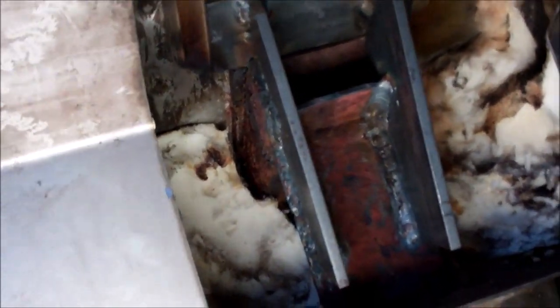I've got the frame rebuilt, and the plate across the top that rests on my repair welds. That stops the evaporator getting squeezed, which is what causes the leaks in the first place.